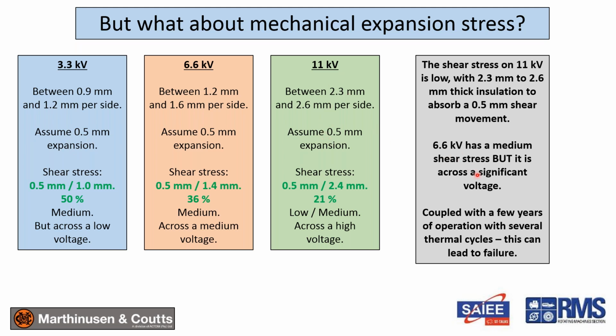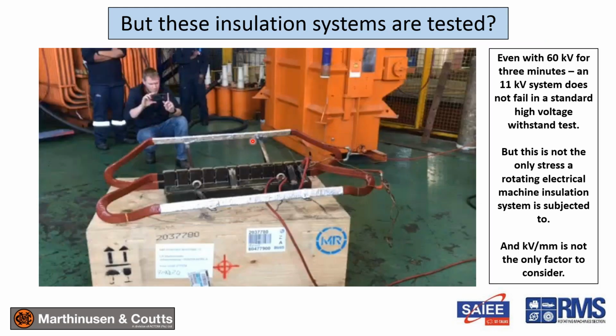So the question asked is why, and most of these, sorry, were on machines that had quite a lot of thermal cycling. These insulation systems are tested, and this video, which I won't play, shows that same coil after the 3-minute 60 kV test failing at 76 kV after about, I can't remember, but just less than a minute. So I mean, it should have failed way before that.